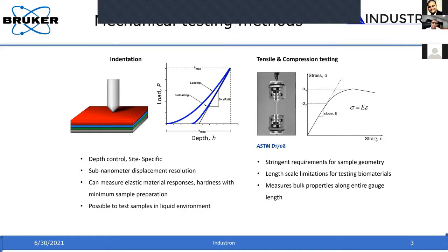Okay. Now, if you take this transducer and combine it with a 3-axis piezo scanner, for example, these scanners are made of tube piezos, quadrant piezos, and these transducers are about half an inch in size. You can mechanically couple to these piezos, and if you apply a voltage onto these piezos in the X and Y direction, you can move those transducers in the X and Y direction as well as in the Z direction. Okay, that helps if you want to place an indent at a specific location, you can do that.